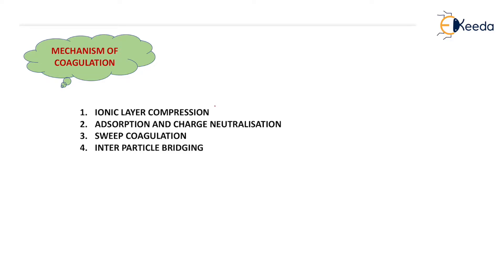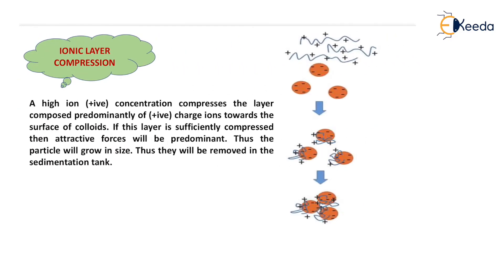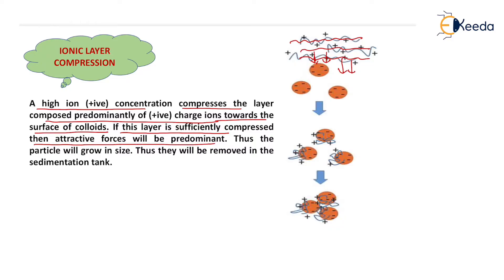The mechanism of coagulation generally takes place in four steps: ionic layer compression, adsorption and charge neutralization, sweep coagulation, and inter-particle bridging. In ionic layer compression, a high positive ion concentration compresses the layer composed predominantly of positive charge ions towards the surface of colloids. When more number of positive charge particles are there, they compress the bottom layer to get in contact with the negative charge. If this layer is sufficiently compressed, attractive forces will be predominant. Thus the particles will grow in size and when the particles grow in size they will be removed in the sedimentation tank.